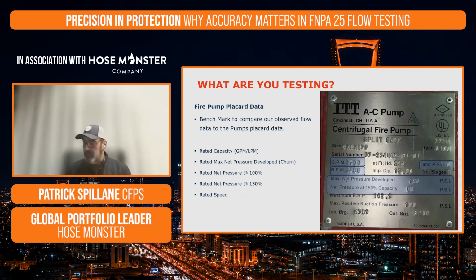So what we're going to do is I'm going to go over an overview of a standard fire pump test, a standard annual fire pump test using a flow meter. And to do that, we have to start with the basis of that fire pump. How is that fire pump designed? Each fire pump should have a placard, an informational placard attached to that fire pump. And it's going to show you some key information about that fire pump and how it should perform when flowing water, depending on its flow rate.